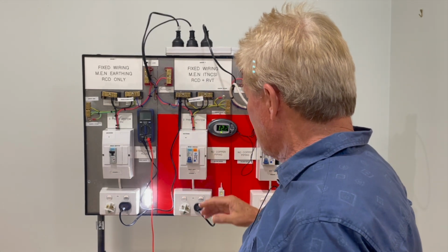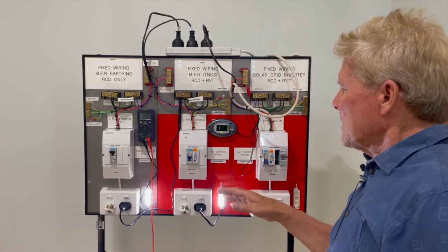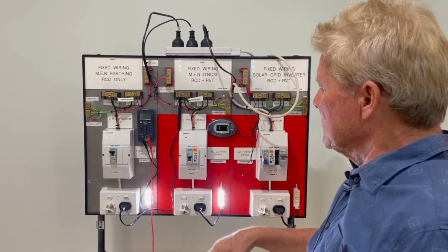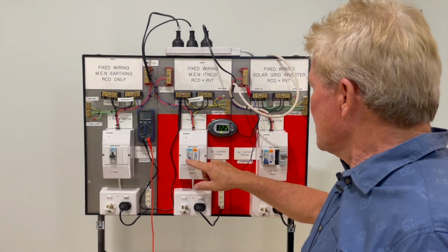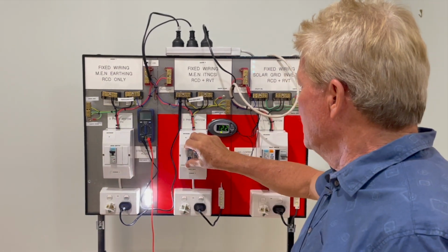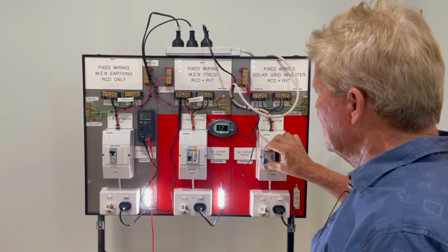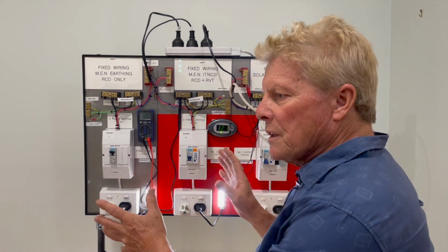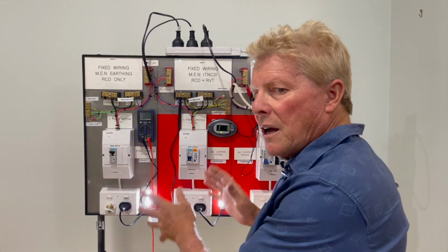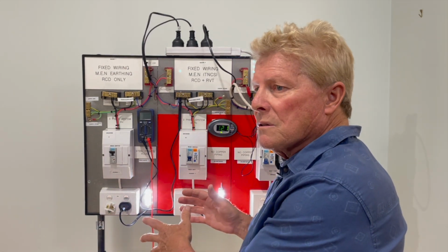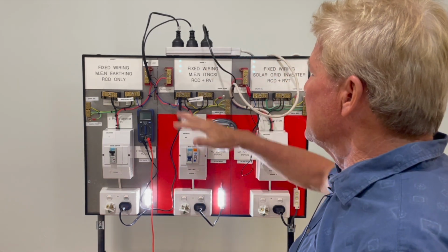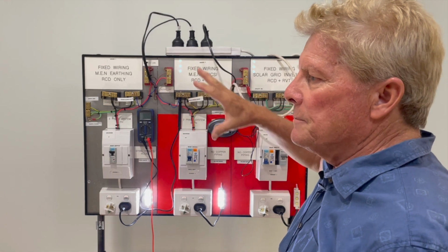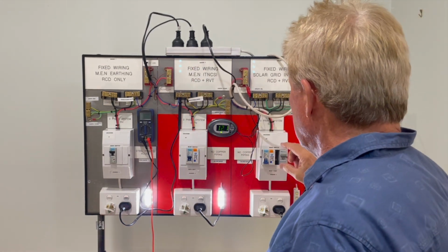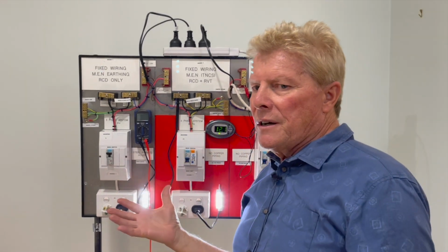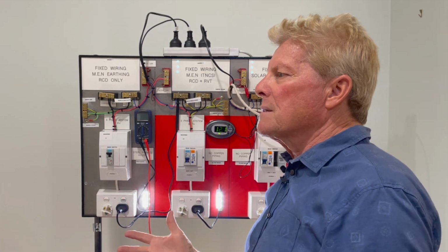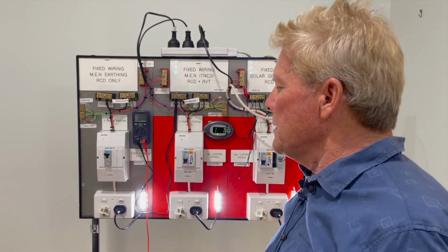We're just going to go through, so we'll turn the load on there. The voltage started probably around about, we'll turn them all off and we'll just show you the voltage. So you get a bit of voltage drop between houses when you turn things on, and that shows you the correlation between the houses on loading as well, not just faults. It's loading as well, as on the transformer. Once you start to load up, it really affects what's going on in your three-phase system. It's balanced. We're just going to demonstrate exactly what happens.